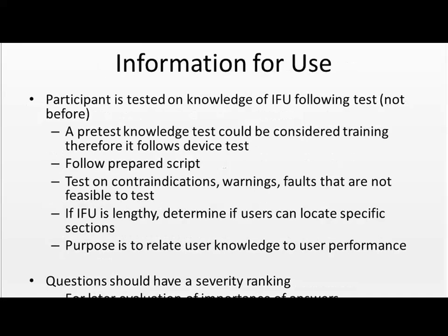Information for use. Following the test, you can test the participant on his knowledge of the information for use. You don't want to do it before because that gives him some extra training. Again, follow a prepared script so that everybody gets the same questions.